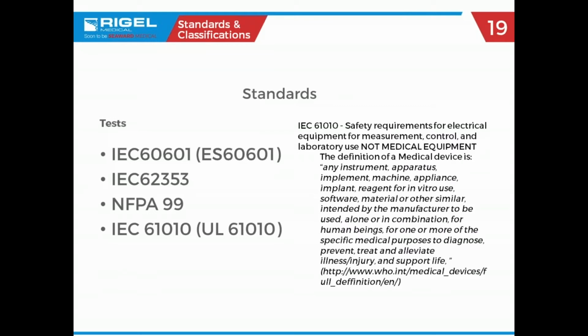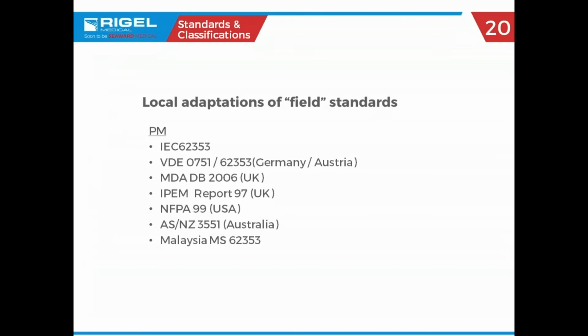And then again, just a little bit more on the 61010. So local adaptations of field standards. So remember back on the life cycle of a piece of medical equipment, we started off with manufacturing and engineering. That is always tested, as we said earlier, to 60601. That's the qualification process. There are pieces of that, such as high pot testing, where you have to put a high potential voltage on the case of the unit through the electric circuits. Specification for that is 2 times your line voltage plus 1,000 volts. So you're putting 1,500 volts on the case of the unit, and you're looking for leakage current.